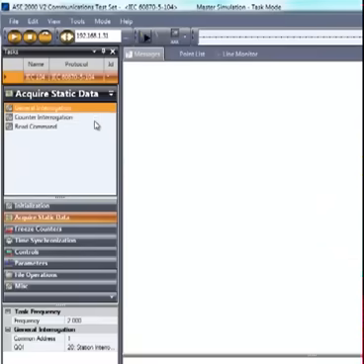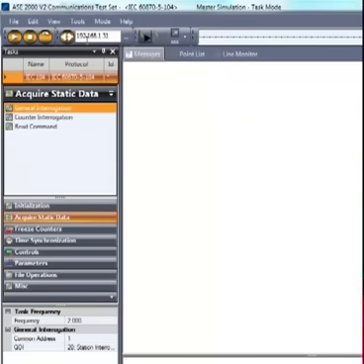The main consideration for 104 protocol is in the communication area. After establishing the IP connection, the master controlling station must send a StartDT message to start receiving data. If the connection is closed, another StartDT is required when the connection is re-established.